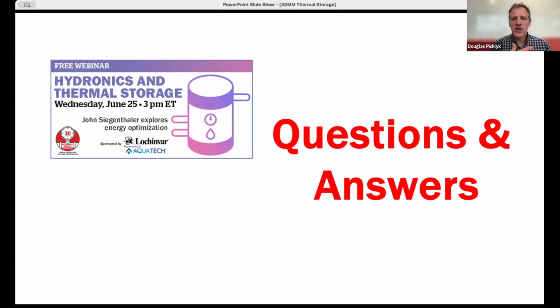In the slide that shows the three tanks piped in series, what is the advantage of having the connection of the last tank being horizontal rather than from the top of the tank? The advantage is you're injecting the water during the charging cycle. If you have hot water coming from the heat pump and you're injecting it into that tank in the upper right corner, if you inject it vertically, and we've seen this with systems with pellet boilers, for example, when you inject into the top of the tank, you're literally creating a flow jet inside the tank, and it stirs the tank and basically destroys the stratification. So the concept is bring that hot water in gently and as slowly as practical, and minimize vertical currents inside the tank. That's why that pipe comes into the tank horizontally.